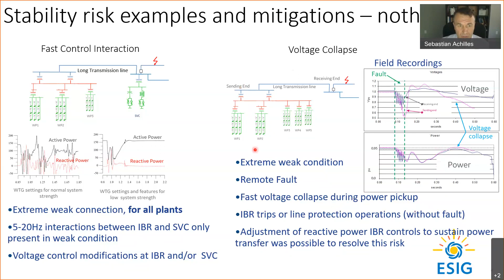So what are the mitigations? From the OEM-oriented description of the mitigations, in some cases you may need to do some mitigations. In some cases, even with low system strength or weak grid conditions, you may find that the system is stable without having to do anything beyond the standard approach. Now, mitigations could include aspects related to making the system stronger, like transmission upgrades with additional lines, avoiding radial operation and having more meshed operation so that the impact of tripping a line is smaller, adding series compensation.